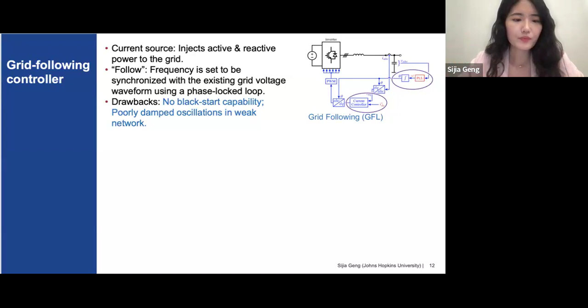The key part in doing so is the phase-locked loop. It wants to establish an internal representation of the terminal AC voltage waveform, and this internal filtered version of the signal can be used for internal control loops. However, grid-following inverters have some drawbacks, such as lack of black start capability and poorly damped oscillations or even instability in weak networks. This is because when the network is weak, the voltage signal is not clean for the PLL to track, and when the inverter injects current, the grid voltage waveform is more susceptible to disturbances from the varying output of the inverter. There is stronger coupling between the two, which may cause bad dynamic behaviors.